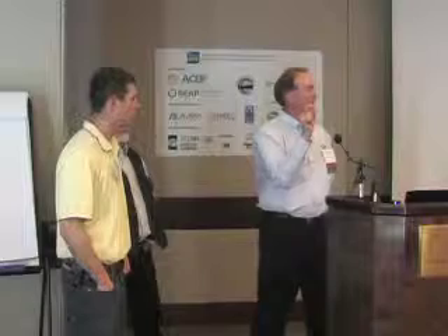What is the parasitic load? You said it was low, I'd like to know for a 100 kilowatt unit. It's about 1.5%, and if it's just sitting there idling, it's almost nil. All of that really comes from cycling it up and down in normal operation. Typically in frequency regulation, we're getting signals every 6 seconds, so it's moving up and down constantly - very seldom do you see that 6 second signal stay flat. It's always moving up and down, so the parasitic load is about 1.5%.